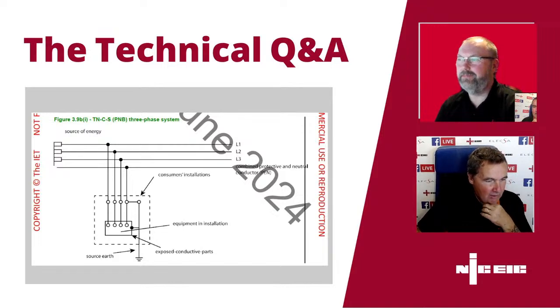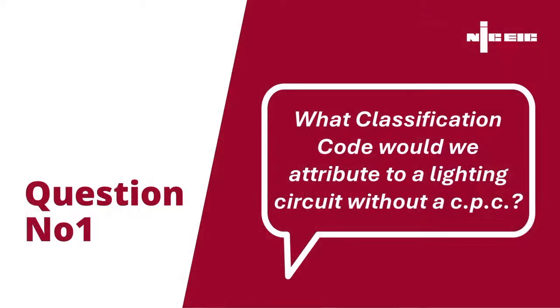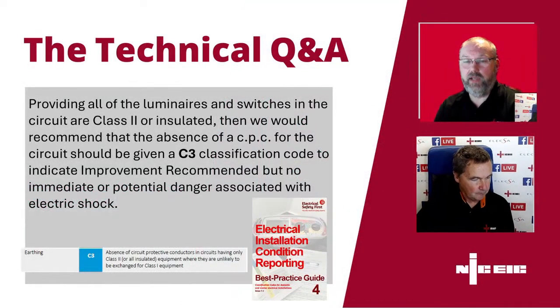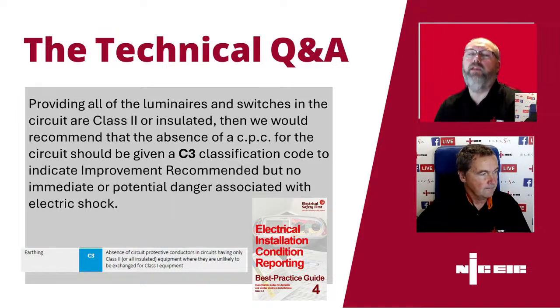Let's look at some of the questions that were hanging about. A classic one we get commonly into the technical helpline: what classification code would we attribute to a lighting circuit without a CPC? Generally, if all of the equipment is Class 2 - so all your lights and switches are Class 2 or insulated - then we can give that a C3. However, if we've got any Class 1 equipment, it may have to be a more onerous code.